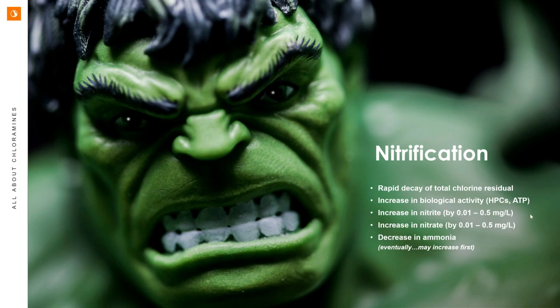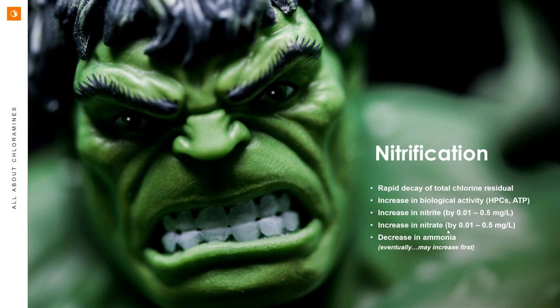So, decreasing chlorine and increasing biological activity markers are things we start to see when we've got a problem. Nitrite starts to sneak up, nitrate starts to go up as the secondary oxidation product, and ammonia is a bit trickier — it can go up initially, which creates the conditions for nitrification to begin, but then it can start to come down as it gets eaten up as food. So ammonia will often be a little high and then we'll see a dip. These are the major indicators — decreasing chlorine, more biological activity, increasing nitrite and nitrate, and a bit of decreasing ammonia.